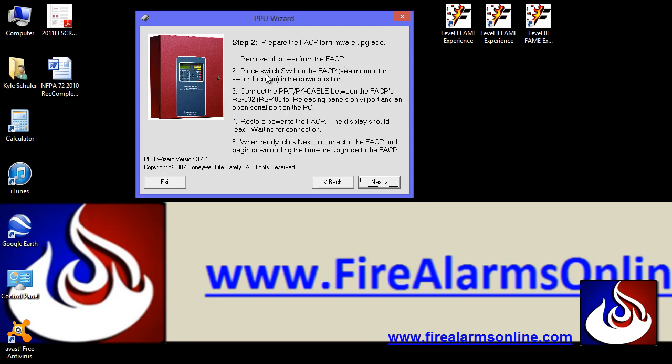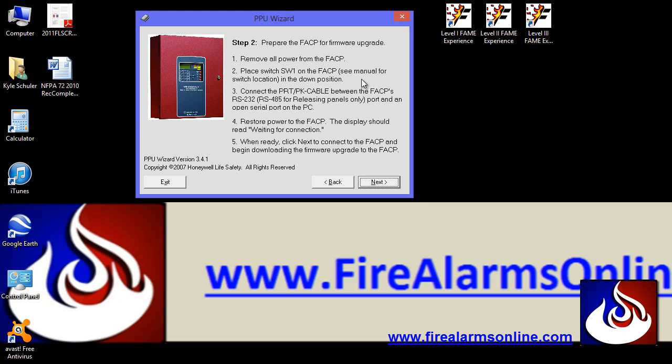And place switch SW1 on the FACP. It says see manual for switch location. I believe it's right behind the display for the panel. But like I said, just check the manual out and make sure you know where the location of it is for each particular panel that you're performing this firmware update on. Go ahead and place that in a down position. And then you're going to connect your programming cable between the FACP's RS232 and an open serial port on your PC, like a DB9.